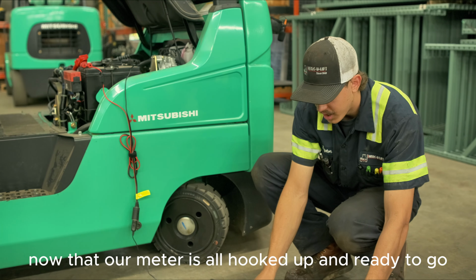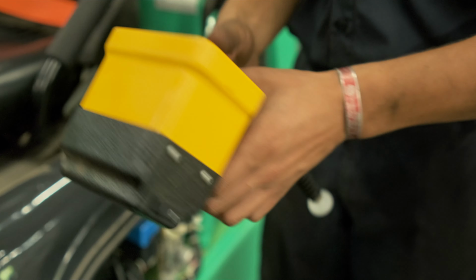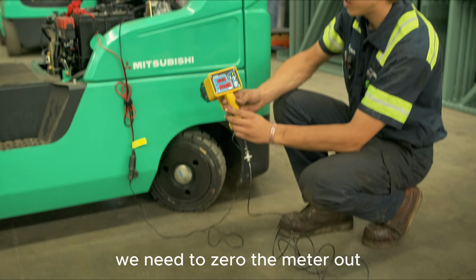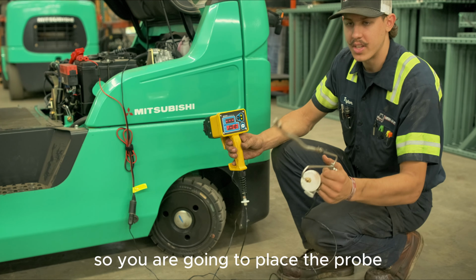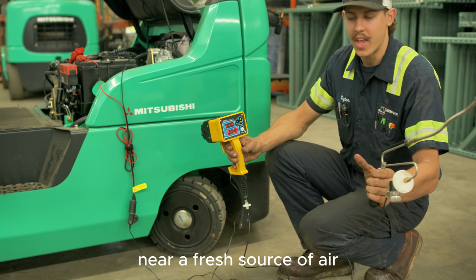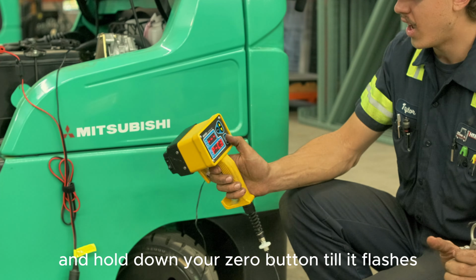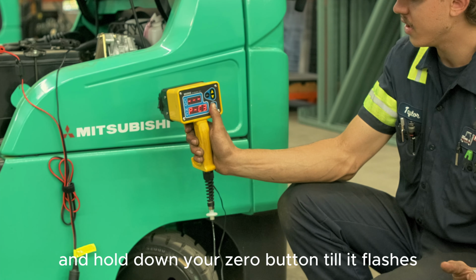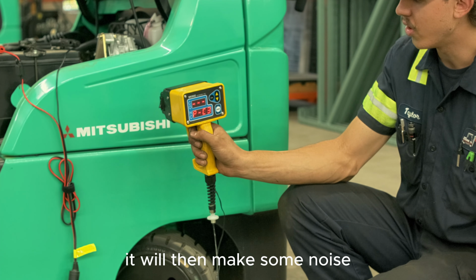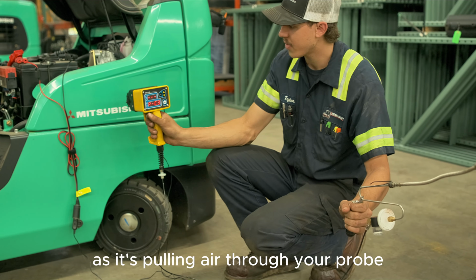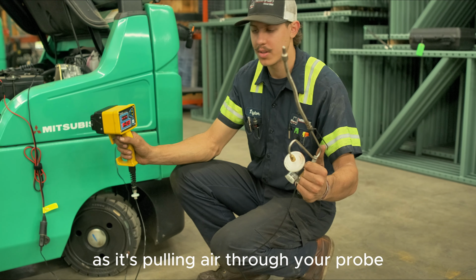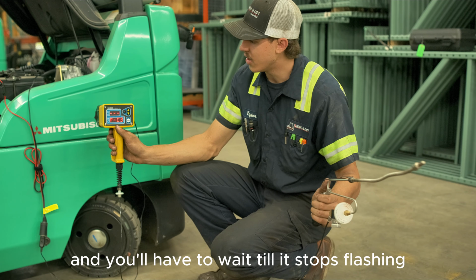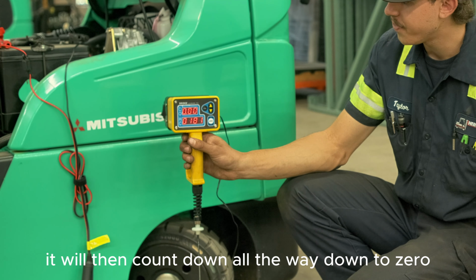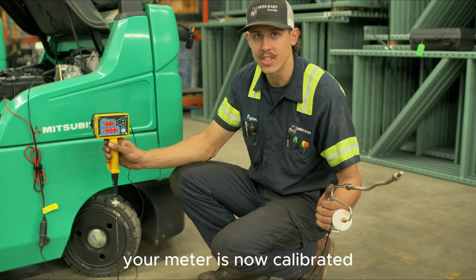Now that our meter is all hooked up and ready to go, we need to zero the meter out. So you are going to place the probe near a fresh source of air and hold down your zero button until it flashes. It will then make some noise as it's pulling air through your probe, and you will have to wait till it stops flashing. It will then count down all the way down to 0. Your meter is now calibrated.